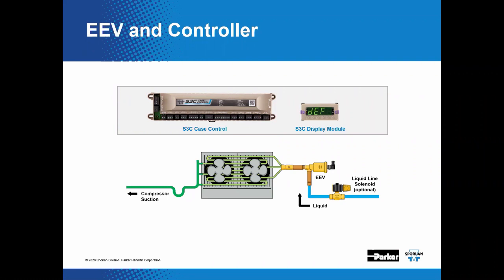This would be accomplished using the traditional cut-in, cut-out method. And the liquid line solenoid valve is listed as optional since refrigerant flow may actually be stopped by closing the EEV. But I kind of like the idea of including this solenoid valve, and I'm not so sure about the optional part. What do you think about that, John? Yeah, I don't think we should really consider them optional. Why is that? Well, in the event of a power failure, the EEV is going to stay in the exact position that it was at the moment of power failure. Oh, okay. And so it's going to keep flowing refrigerant whether the case needs it or not. Okay, I got it. And so you could have some issues with flooding there.